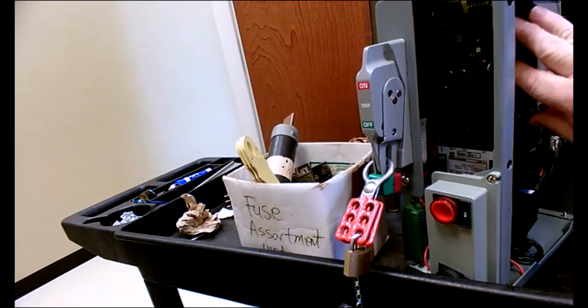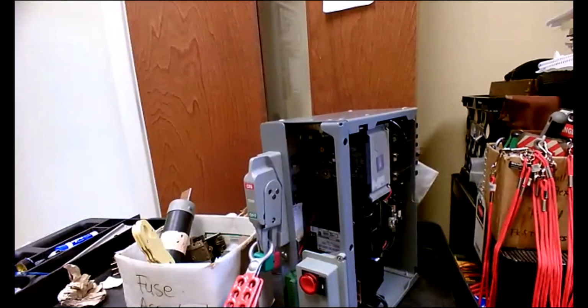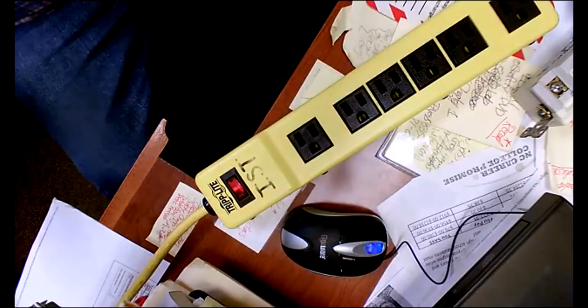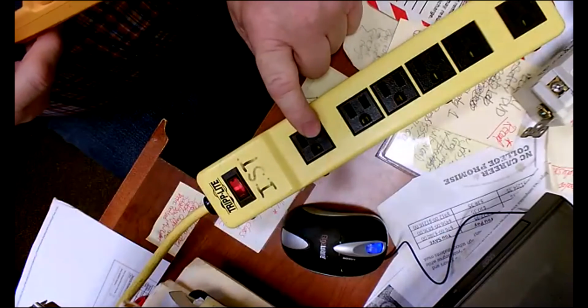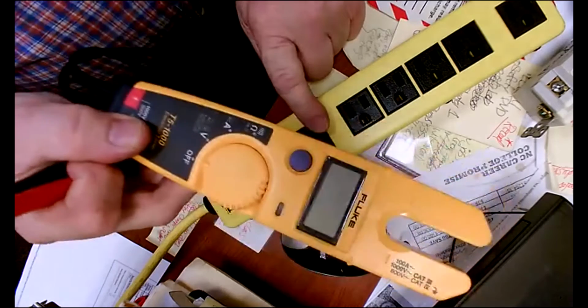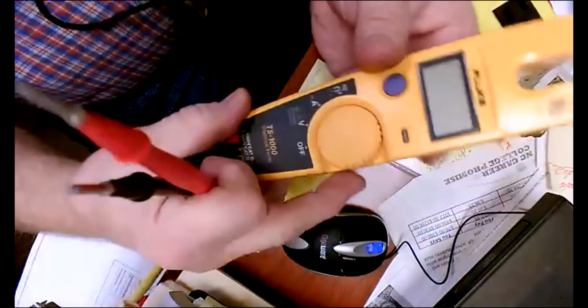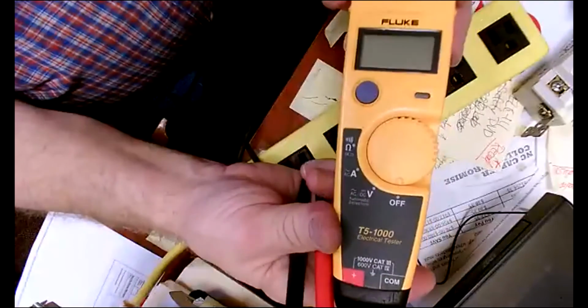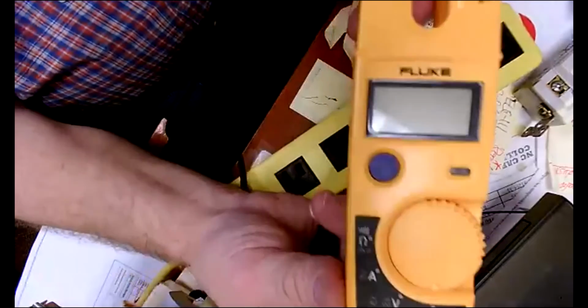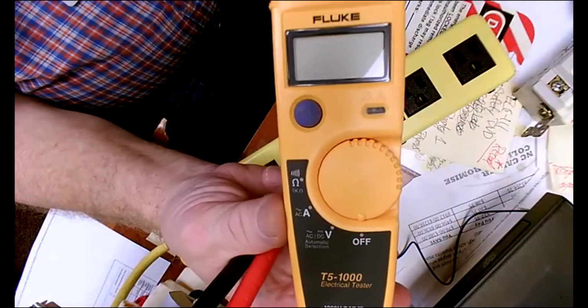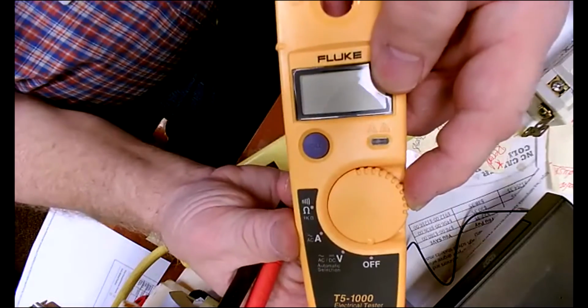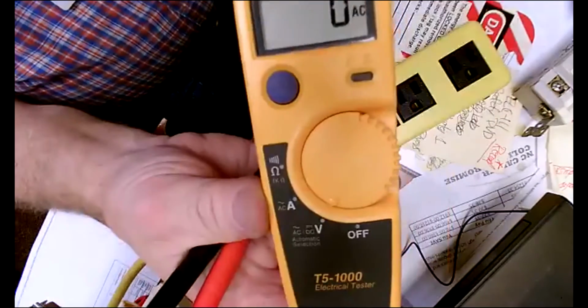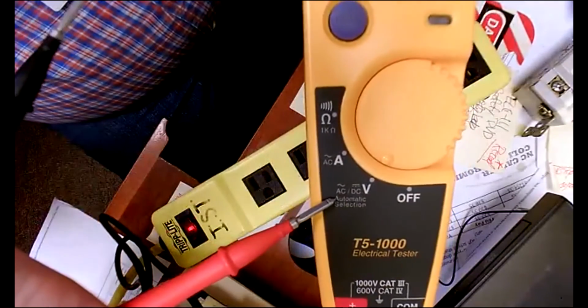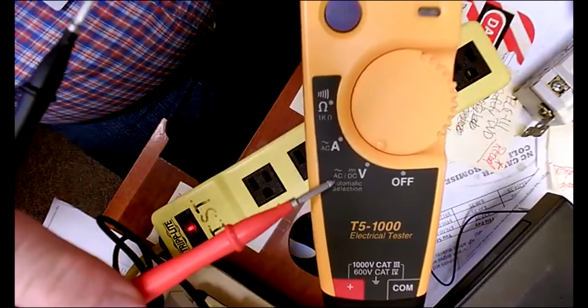Okay. Now, before you actually test to see if it's dead, you want to do this. They tell you to go to a power source that you know is hot to verify that the meter is working properly before you go check that dead circuit. So we're going to go here, and on the meter, if I'm going to check voltage, what do I put the meter on? You put your meter on volts. And for volts, it says it'll pick up AC or DC automatic selection. Do y'all see that? Yeah. So it detects either one.